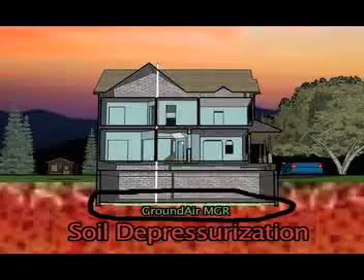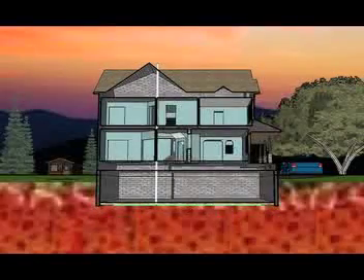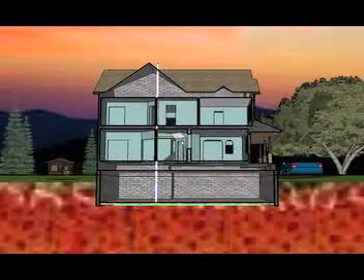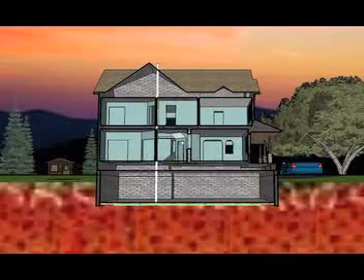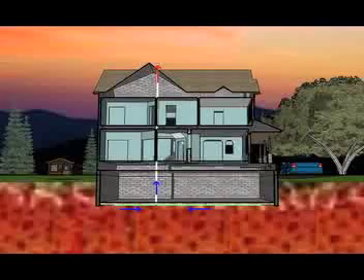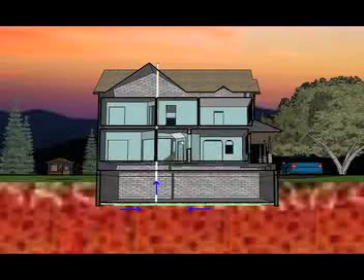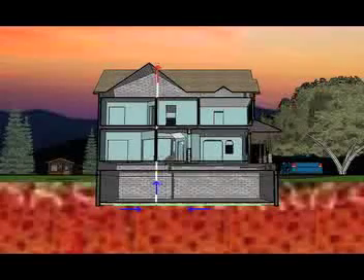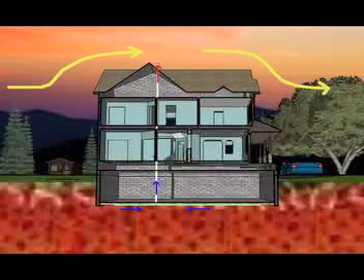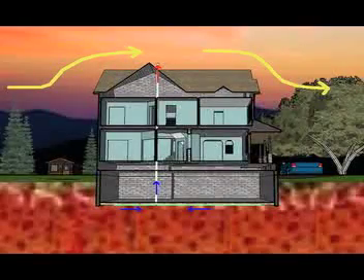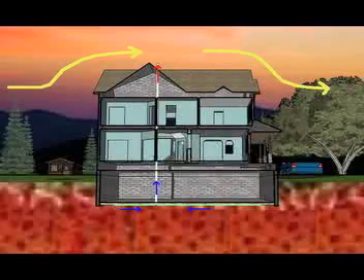As air collects in the vent pipe leading through the roof, it becomes heated as it goes through the heated space of the house. This air naturally wants to rise, and as it does so, it creates a stack effect within the pipe. Wind, as it travels across the top of the pipe, creates a low pressure zone at that location, additionally drawing air up the pipe.